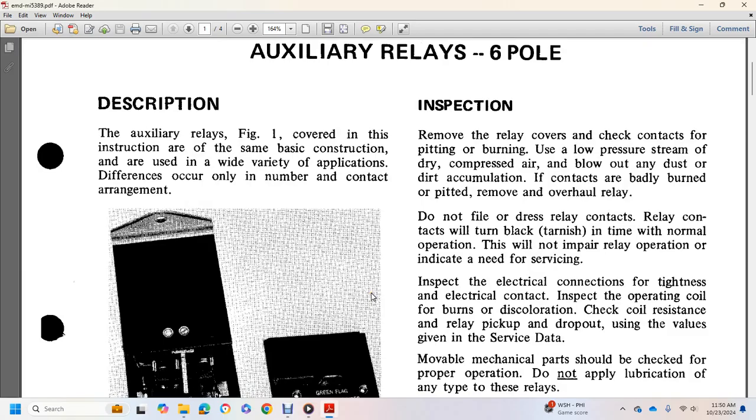Inspection: Remove the relay covers and check the contacts for pitting or burning. Use a low-pressure stream of air to blow away any dust or dirt accumulation. Contacts that are badly worn or pitted require relay overhaul. Do not file auxiliary relay contacts. Relay contacts will turn black with a varnish-like coating during normal operation over time. This will not impair relay operation and does not itself indicate a need to inspect electrical connections.